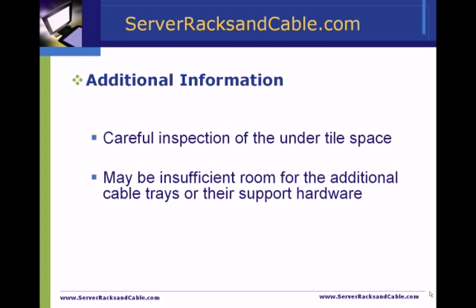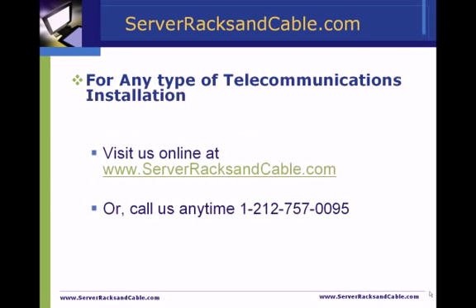Because of piping, power lines, alarm circuitry, and other things under the tiles, there may be insufficient room for the additional cable trays or their support hardware. The same considerations apply to over the cabinet or above the ceiling tiles cable ducting when used to hold Cat5e cabling which is being changed to Cat6. On-the-job experience is extremely important, helping to make sure you do not overlook all the necessary details that have to be considered to provide an accurate and on-time job completion.